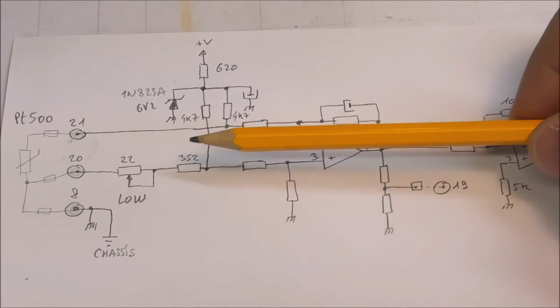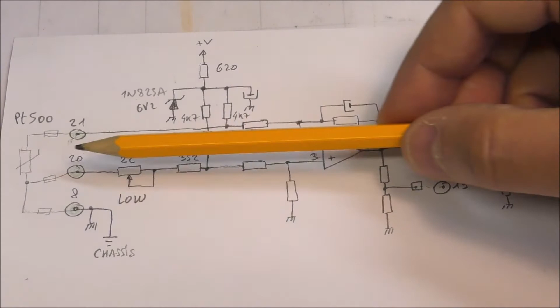The sensor itself is connected between terminal 21 here and the ground. And there is another connection at pin 20, which is actually connected to the ground of the sensor. This permits effectively the compensation of the resistances of the wires, which are represented here.